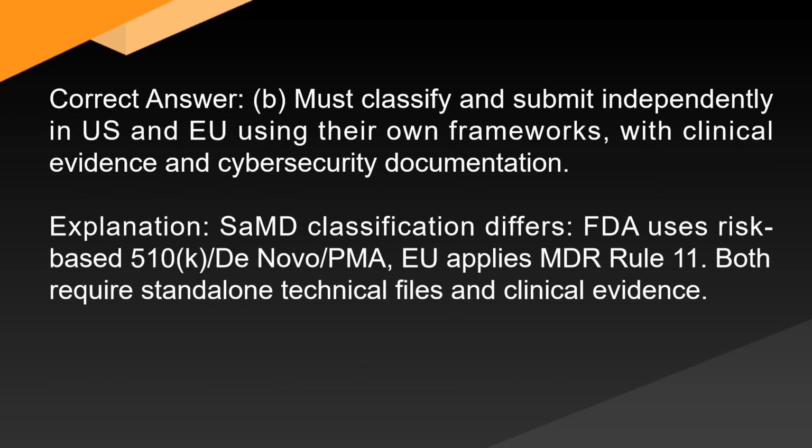Correct answer. B. Must classify and submit independently in US and EU using their own frameworks, with clinical evidence and cybersecurity documentation. Explanation. SaMD classification differs. FDA uses risk-based 510(k)/de novo/PMA. EU applies MDR Rule 11. Both require standalone technical files and clinical evidence.